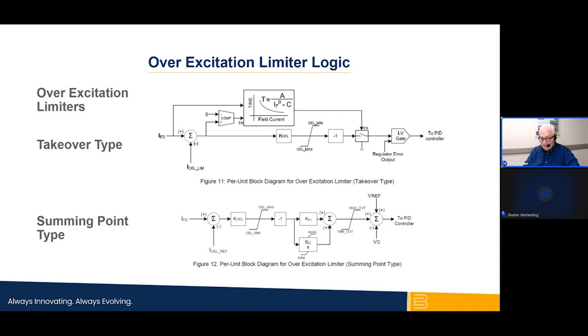You should expect to encounter overheating, or heating approaching the thermal limits, with prolonged operation with field current amplitudes above that rating. The input signal to the digital voltage regulator that is used to detect overexcitation is usually an output of an isolated field current transducer, which provides a small DC signal representing field current, or in some cases, a signal representing field voltage. The overexcitation limiter is dependent for its function on that input. The heating effects that raise the temperature of the field windings are proportional to the square of the field current. The action of the excitation system controls includes limiting the continuous field current. The pickup point for the limiter is established from the limit based on what we find in review of the documentation. Take note of this slide's takeover limiter, which is the top of the two.